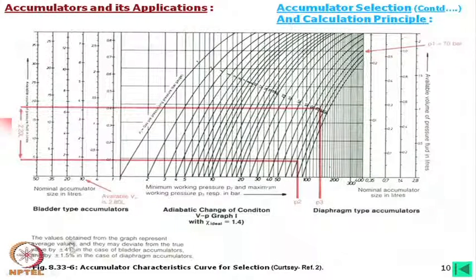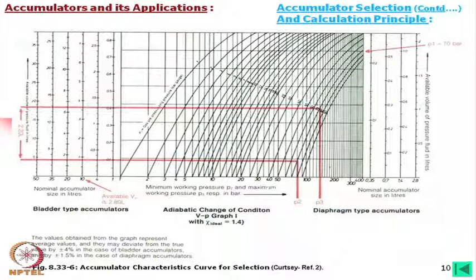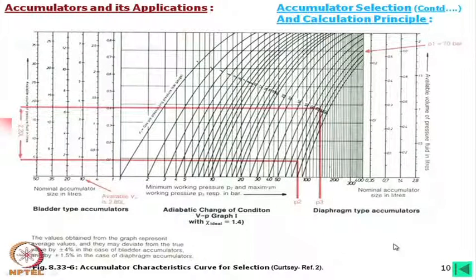The manufacturer's selection graph shows curves for bladder type and diaphragm type accumulators, plotted on N = 1.4. Tolerances are also given. If the required working volume is 2.20 liters, one might be tempted to select a 4-liter accumulator, but in that case the pressure range may not be optimal — the graph should be studied carefully to make the right selection.